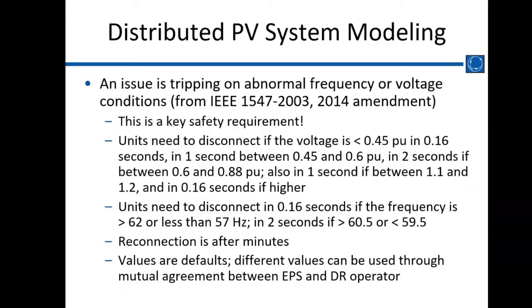So when an event happened and a whole bunch of generation got tripped and the frequency dropped, a huge amount of load saw this frequency drop and all left at the same time when they didn't really need to. I think they ended up with an over-frequency event in the end. They had a big gen trip, but then lost way more load than the generation they had tripped, and that was the problem. That's where all the momentary cessation stuff came from.